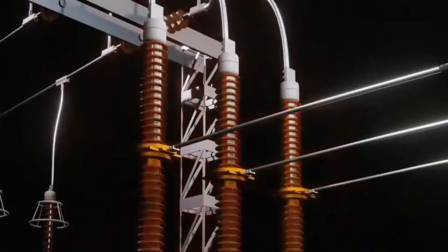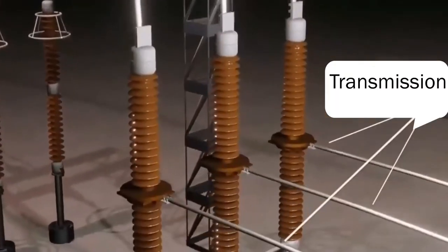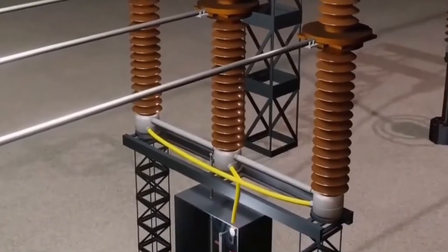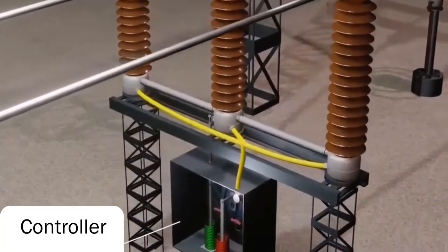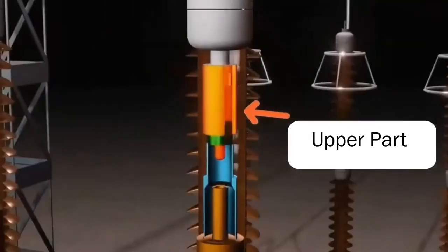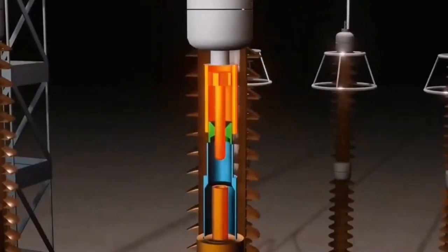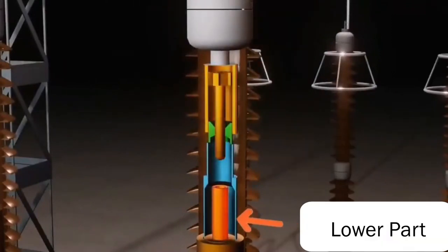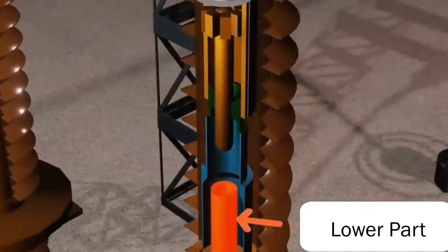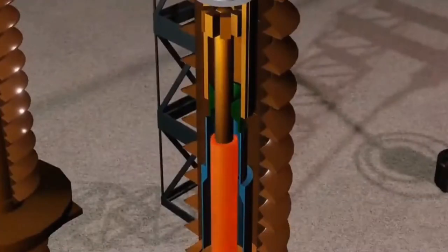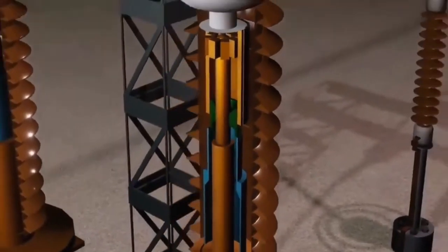The upper part of the circuit breaker is connected to one end of the transmission line, the middle part is connected to the other end of the transmission line, and the lower part is connected to the controller of the circuit breaker through a mechanical device. Its upper part is made of copper. And the fixed lower part is also made of copper, but it is hollow and can be moved to connect with the upper contact to complete the circuit. The issue is how the lower contact can move upwards.